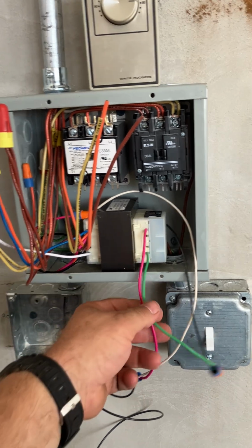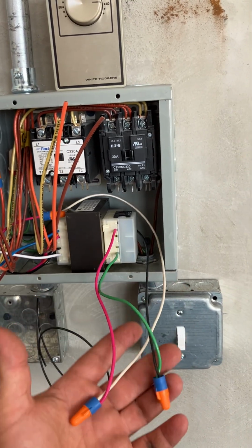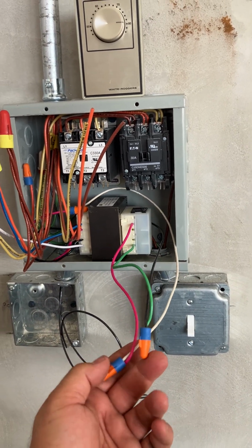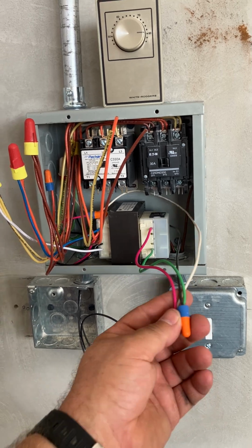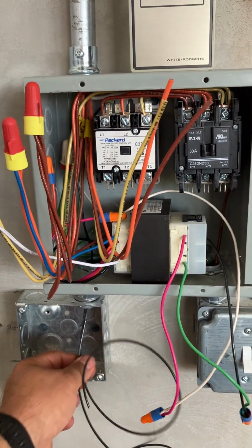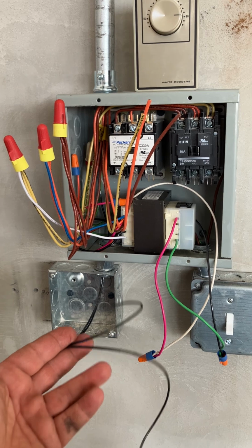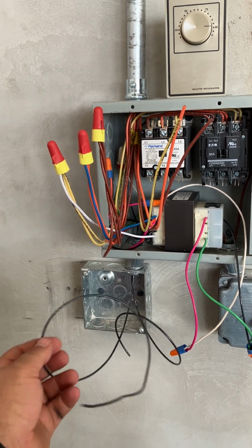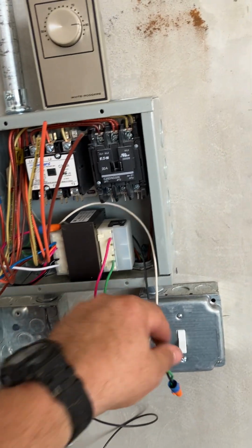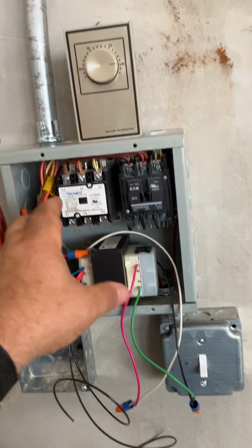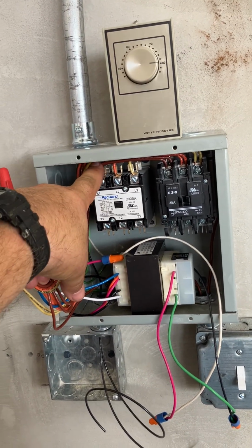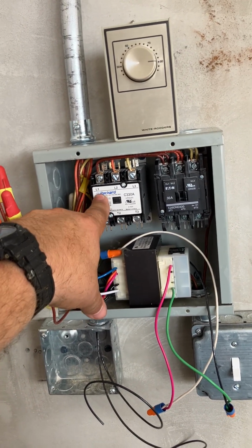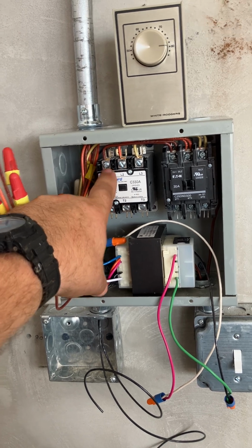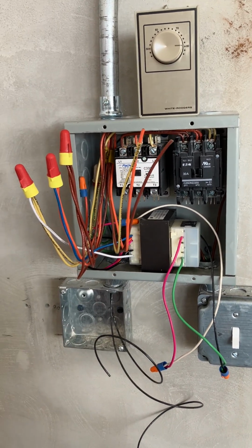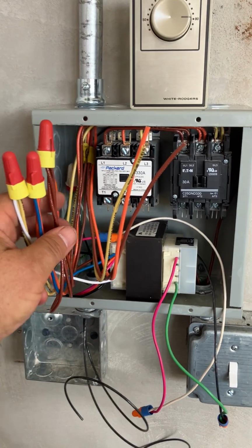Going into the transformer, and then coming out the other end, the secondary side of the transformer, we have our 24 volt right here, feeding down to the thermostat. Essentially that's hot and switch leg. And then the white wire, number 16 wire, control wire, goes to the coil of our 24 volt coil contactor right there. I hope I'm not running out of time here.